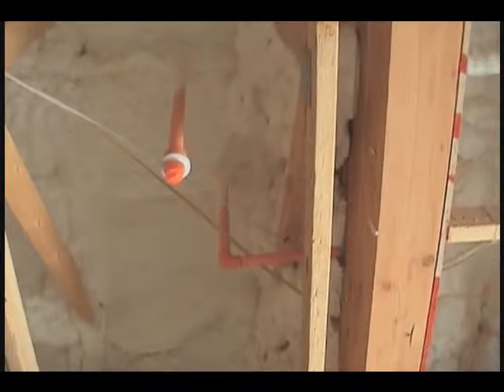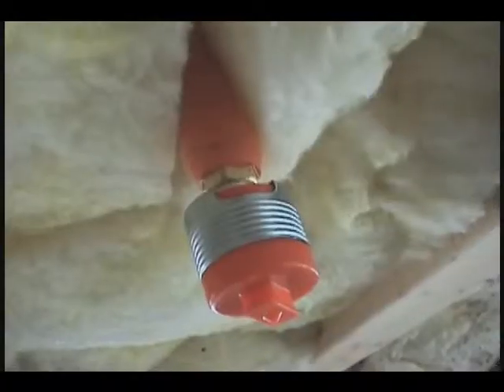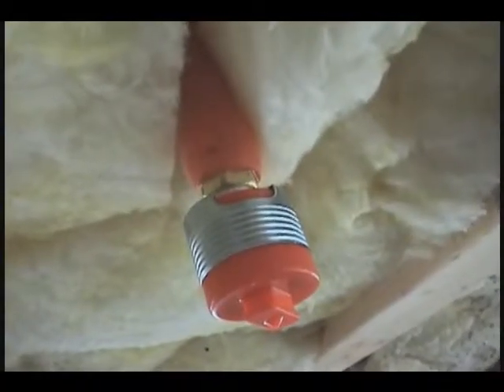One common misconception about fire suppression systems is that if one sprinkler goes off, all the sprinklers throughout the house go off. That worries a lot of people about putting one into their home. However, the new systems from the last 5 to 10 years don't have that problem. If there's a fire anywhere in the house, only the sprinklers that heat up to over 135 degrees will discharge and release water, so the rest of the house won't be affected unless the fire spreads to other areas and triggers those sprinkler heads too.